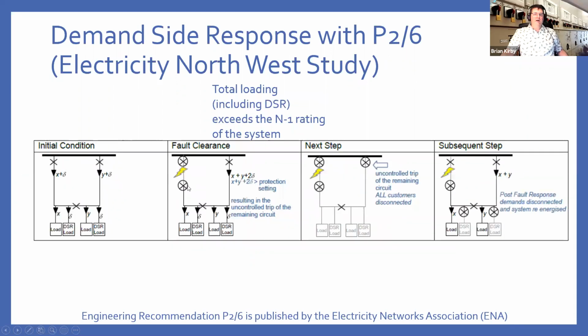Now, in that scenario, you get the fault. You go from a healthy system to a fault on the one feeder. This time, your load exceeds the setting for this line. So now this line trips as well, and you've lost all your load. What you do then is you reconnect your permanent load, but your DSR does not come back on. And that gives you a quicker response to restore your load, because you've shed some of the load that was there prior to the second line tripping.